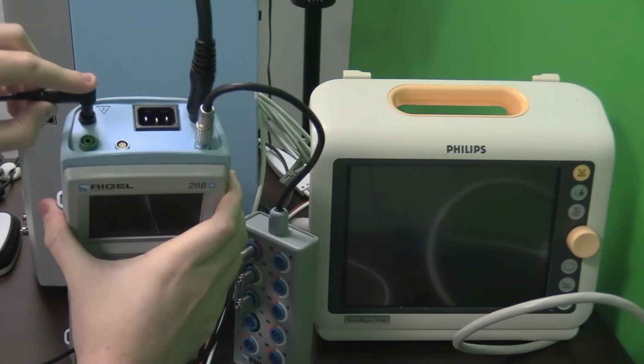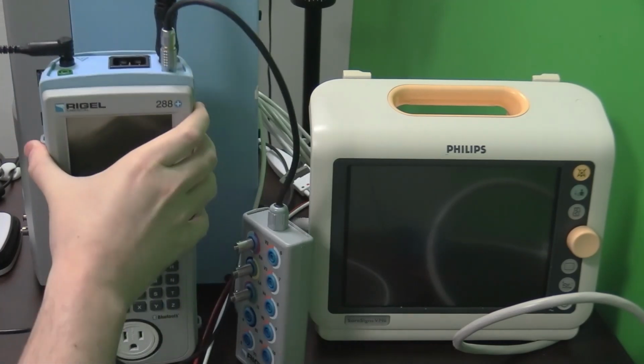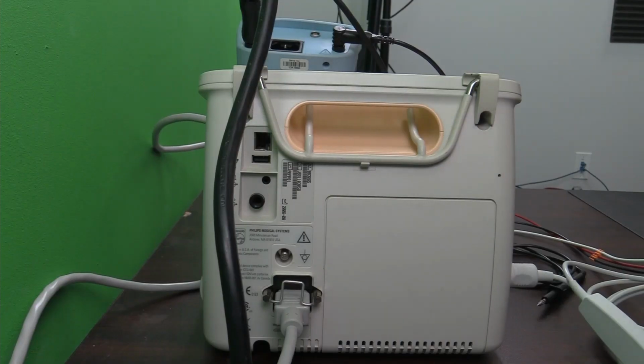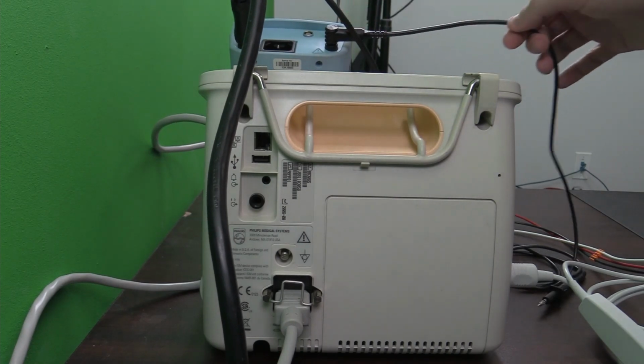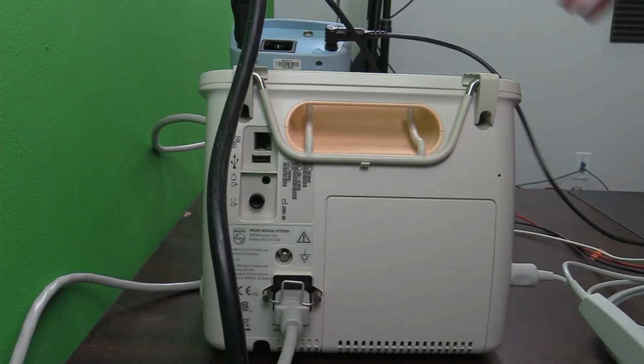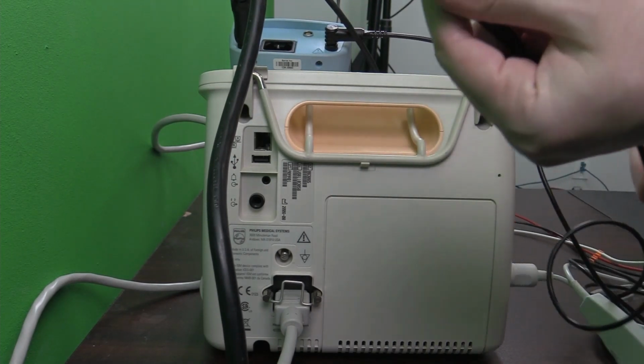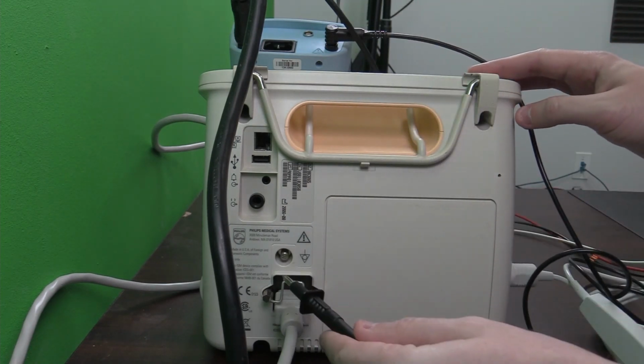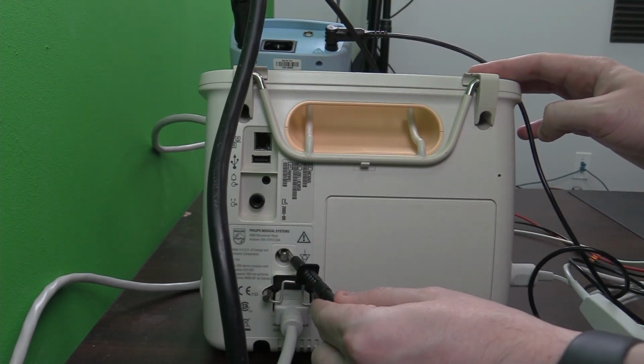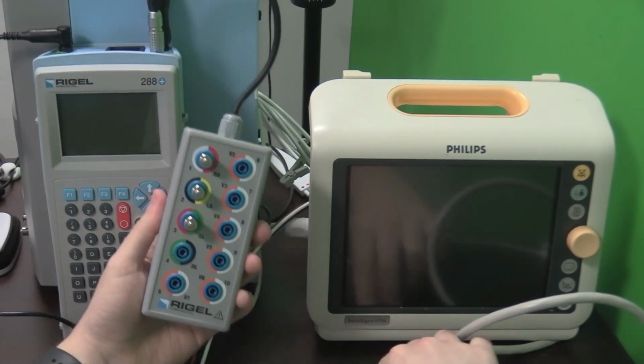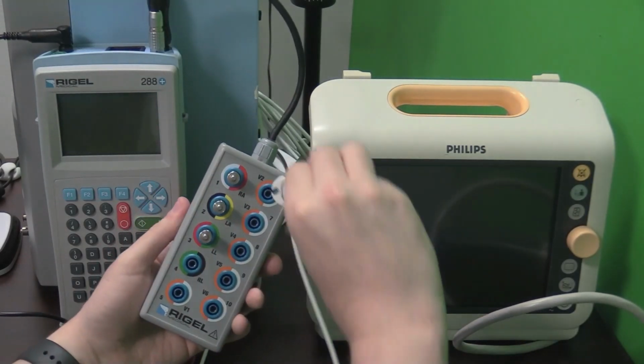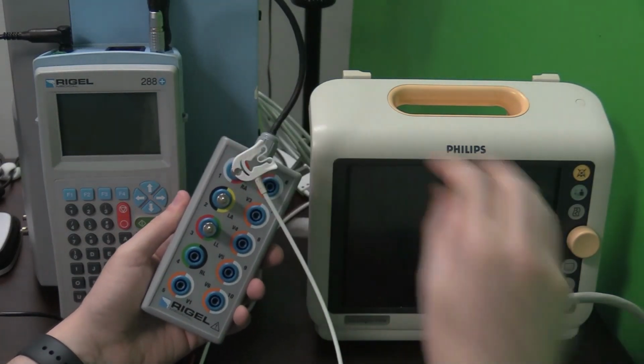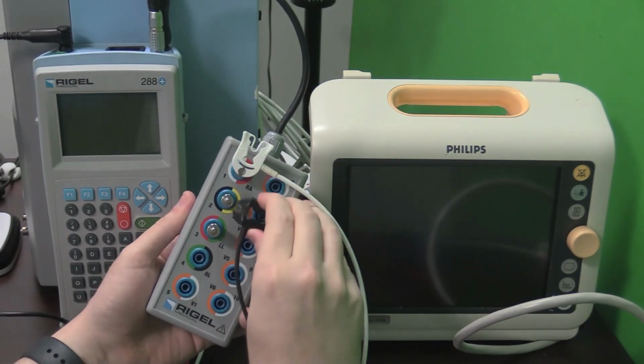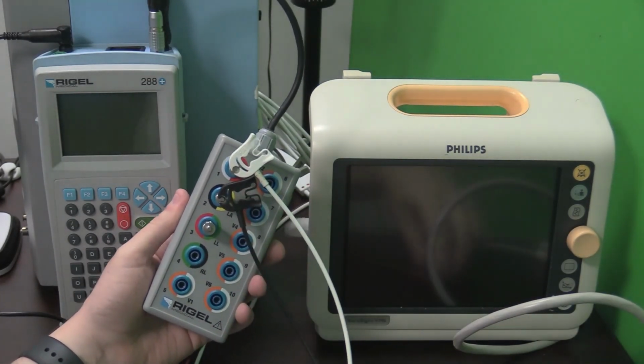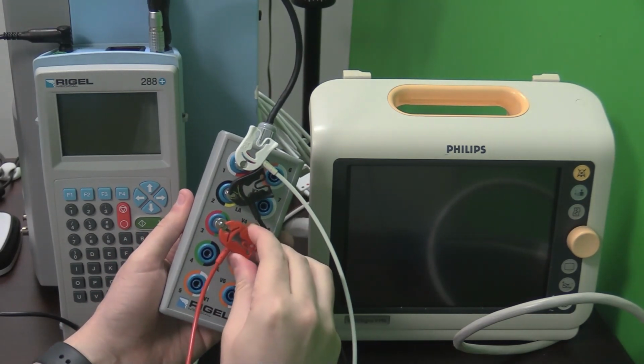Next, you're going to take your earth bond test probe, plug it into the black connector on the back of the device. Now that the earth bond test probe is connected, you're going to take the probe itself and connect it to the back of the Philips monitor at the ground lug. Now you're going to take your applied parts box and you're going to start connecting your ECG leads. I have 3 lead ECG, so I'm going to connect the right arm, the left arm, and then finally the left leg.